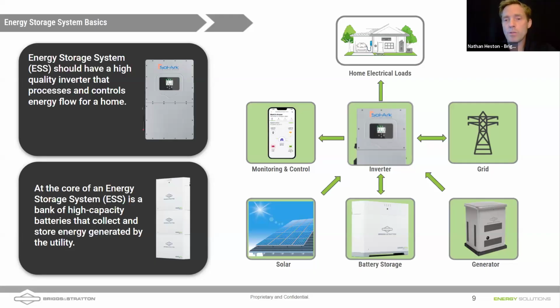The inverter and the batteries are also capable of communicating information, and we can monitor and control that with remote apps. And additionally, if that battery gets low, we can integrate a generator and have that generator provide backup power, such that the generator charges the battery, covers the home loads for a short amount of time, and then shuts itself off. And we minimize the amount of fuel use when we have energy storage. So a lot of great options.